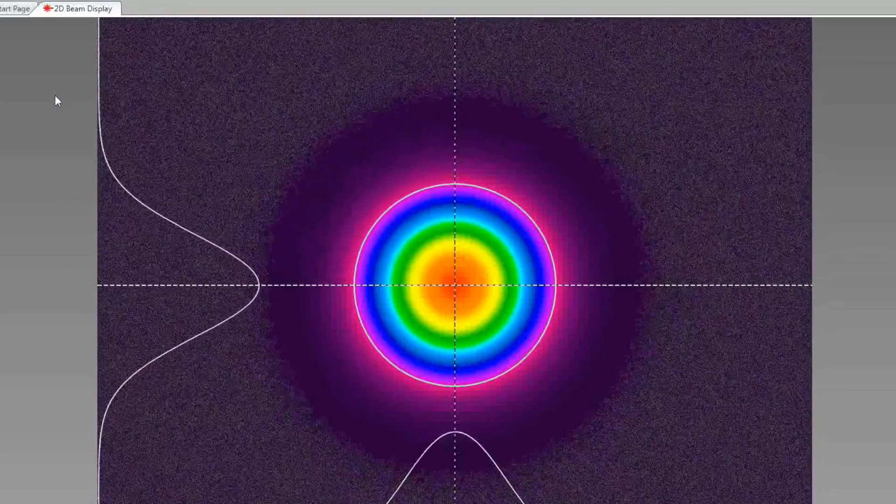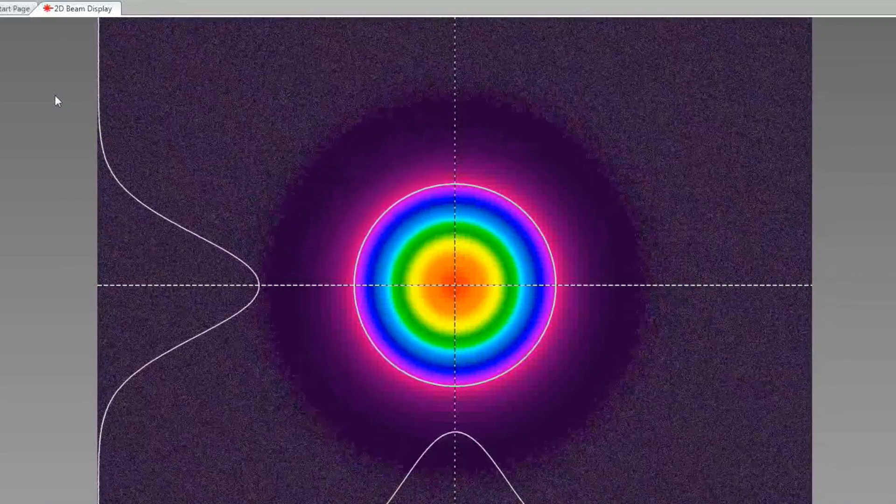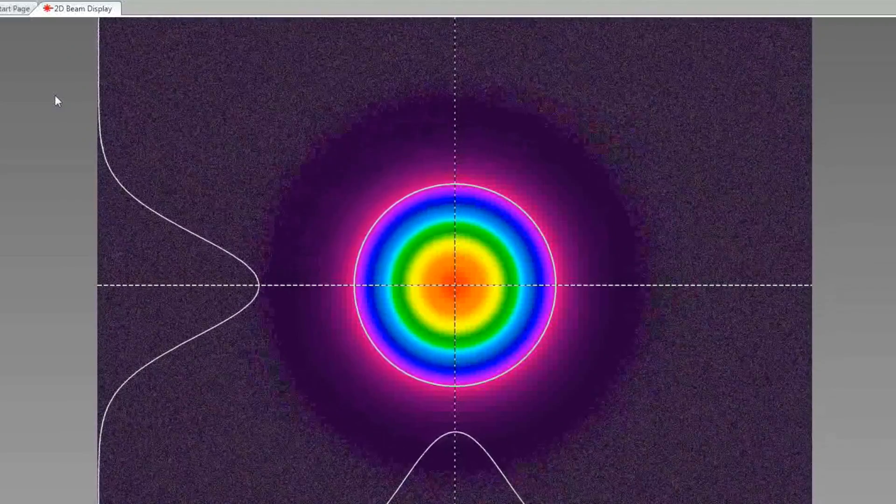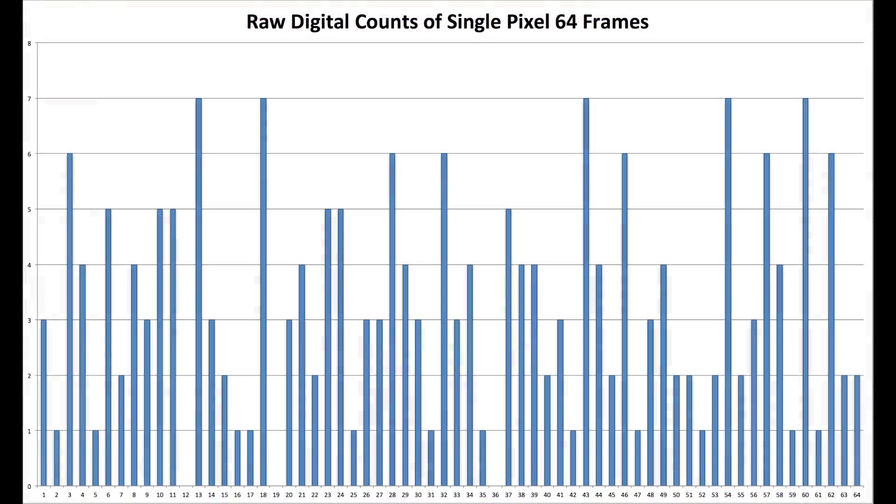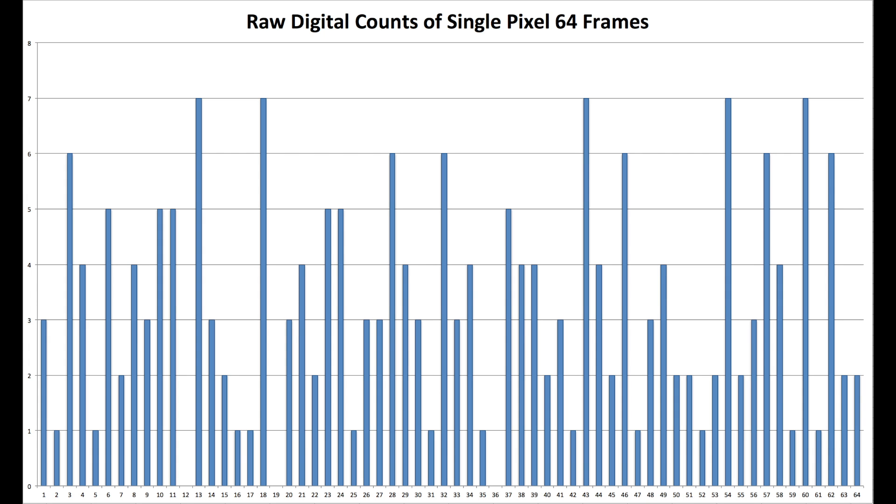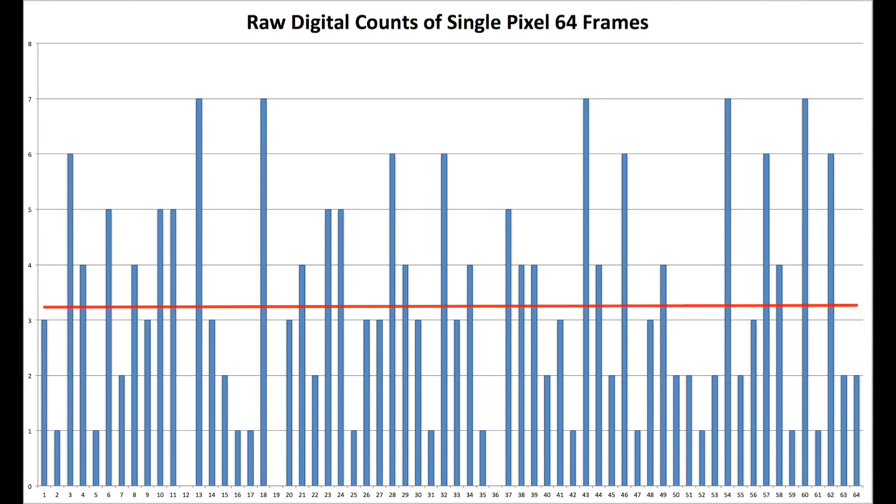Let's examine background noise from one pixel before UltraCal. This graph shows the values from 64 frames. Some counts are higher than others. UltraCal calculates the average of these counts and sets a true baseline.